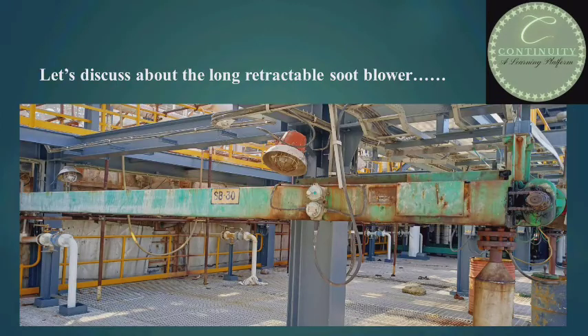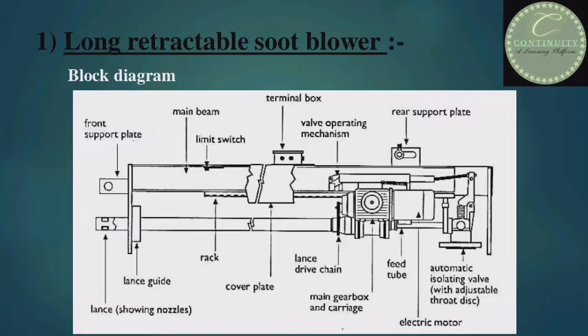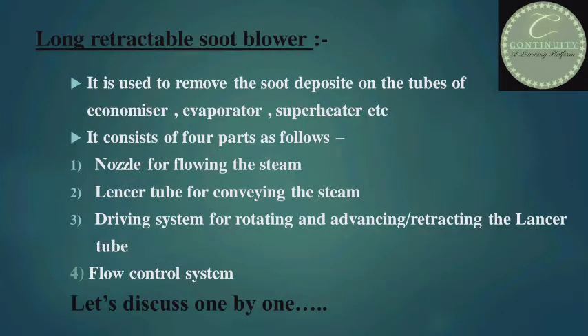Let's discuss about the long retractable soot blower. Look at the figure — this green object is the long retractable soot blower. This is the block diagram of the long retractable soot blower; all parts of this soot blower are mentioned here. Long retractable soot blower is used to remove the soot deposit on the tubes of the economizer, evaporator, superheater, etc. It consists of four parts: first, nozzle for flowing the steam.